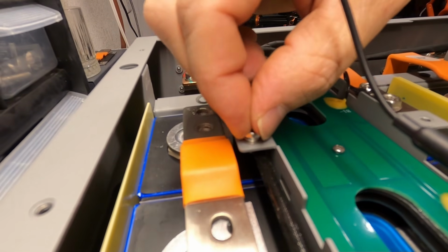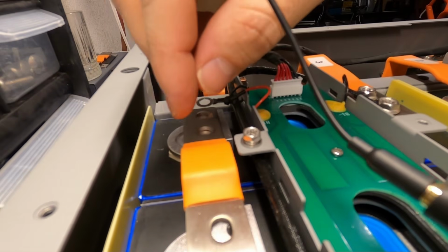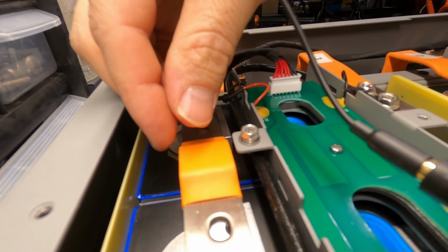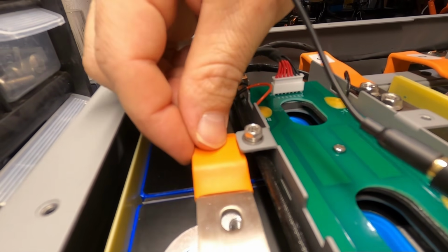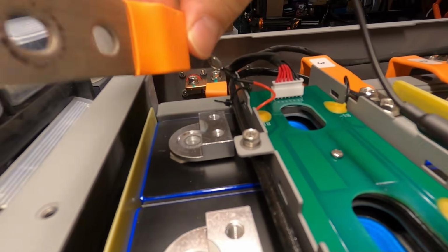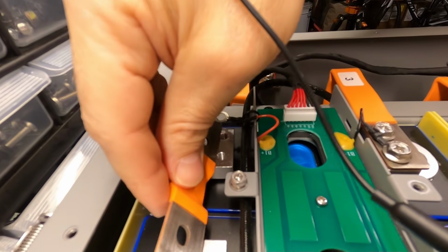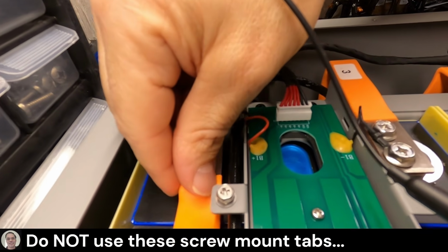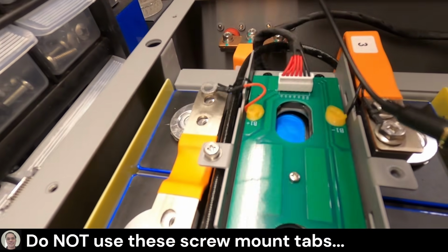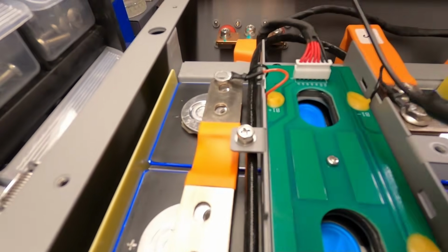That screw is protruding through the threads on the other side of that tab. If I were to slide the bus bar in there, now it's insulated, so it's not going to do anything, but it's hitting the screw. So what we can do for this, besides not using that screw, is put the bus bar upside down so that it clears the screw.